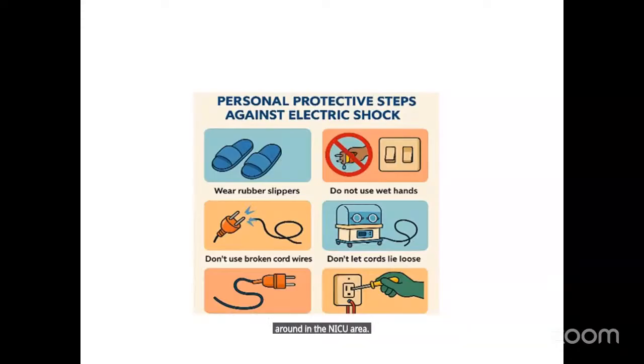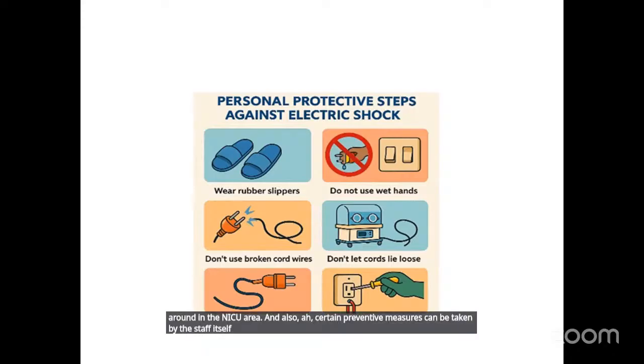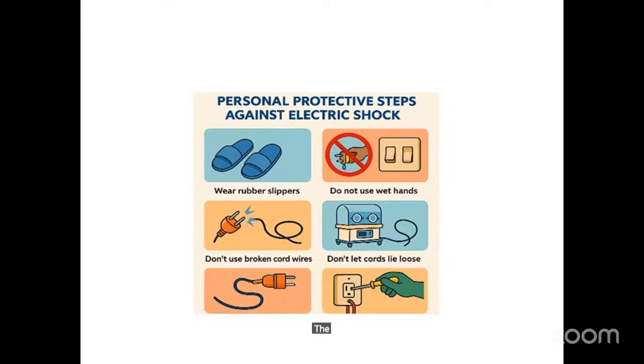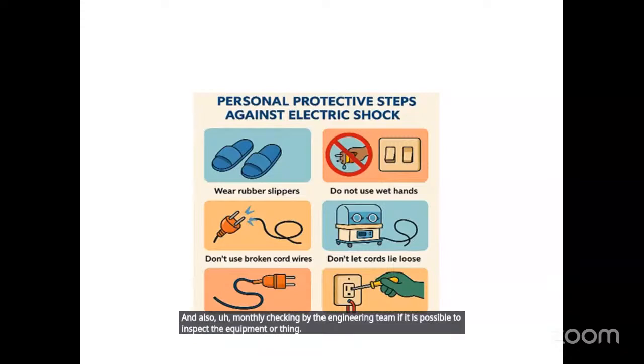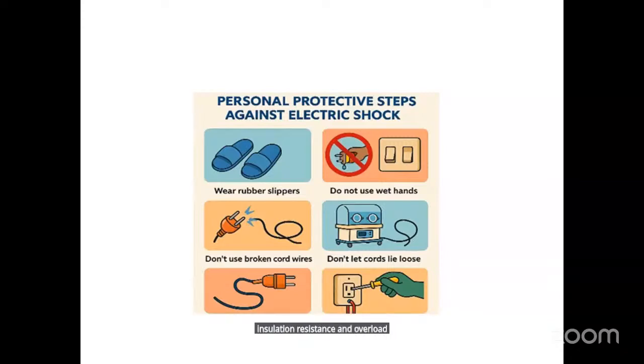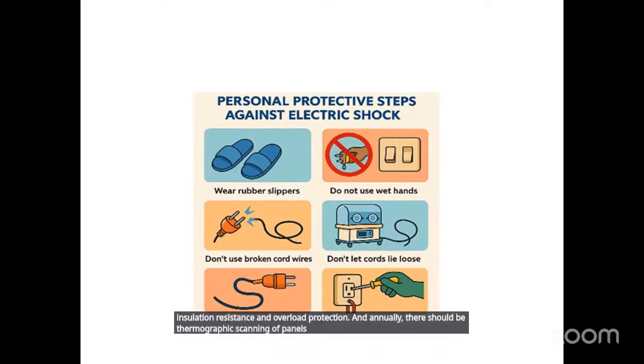And also, certain preventive measures can be taken by the staff themselves in an ICU. Daily, the nursing staff should visually check the plugs, cords, and sockets for damage before their use. And also, monthly checking by the engineering team, if possible, to inspect the equipment earthing, insulation resistance, and overload protection. And annually, there should be thermographic scanning of panels to detect overheating, and full load testing of the circuit should be done.